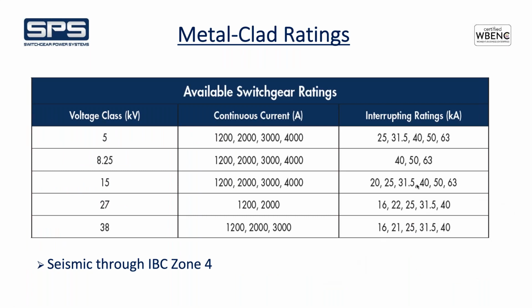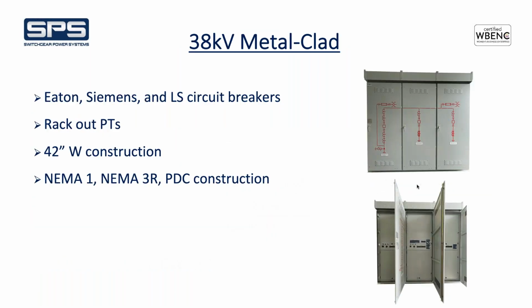So I mentioned we do build metal clad switchgear, and from 5 to 38 kV, 5 kV and 15, we do 4,000 amp, well, a little lower amperage at the higher voltages, up to 63K, 15 kV. And we also do build 38 kV metal clad switchgear. So we believe that the metal enclosed circuit breakers is a great alternative to metal clad, but we recognize that there are customers who do prefer metal clad switchgear with the draw breakers, and we do build that. Eaton, Siemens, and LS circuit breakers are who we offer. Rack out PTs at the higher voltage, and NEMA 1, NEMA 3R non-walk-in, and PDC construction.